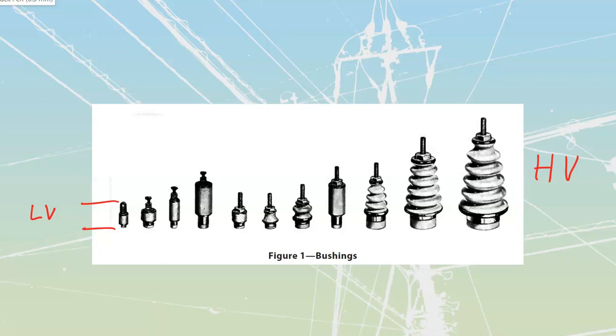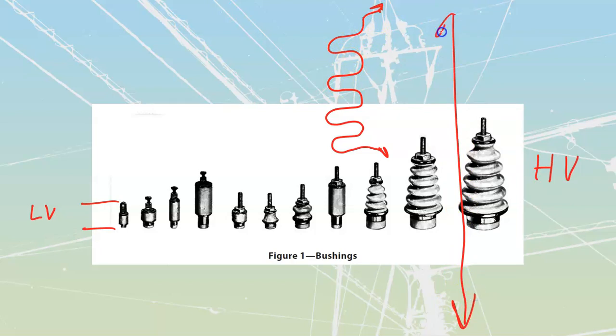As soon as we add this skirting, in essence we now have a path that is way longer because it's a zigzaggy path. If I'm going all the way over from the top of my bushing to the conductor on the inside, I'd have to travel over the top of that, and if you stretched that squiggly line out, you'd see that it's very, very long.